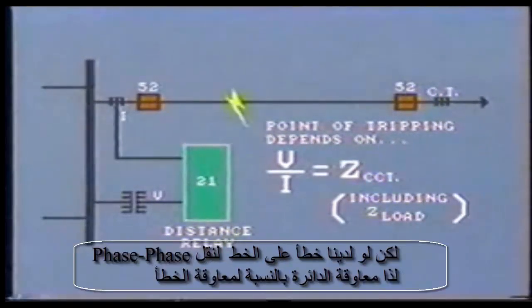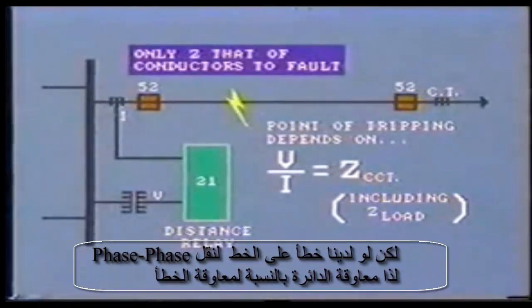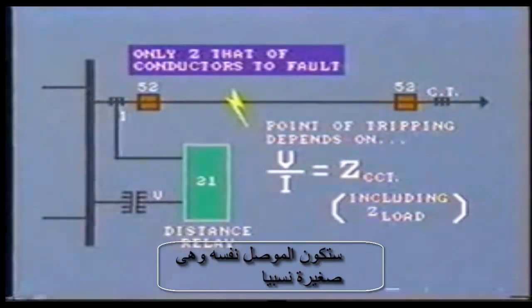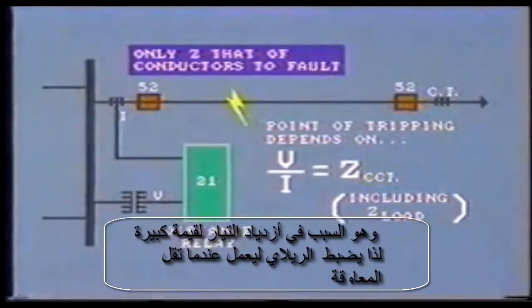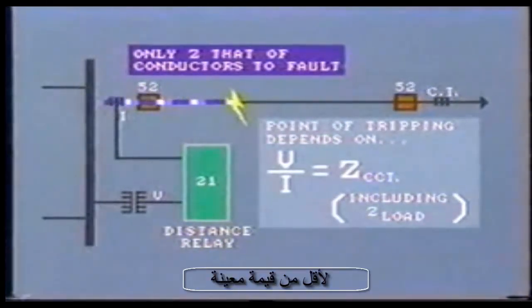However, if we have a fault on the line — say, a direct phase-to-phase fault — then the circuit impedance to the fault is only that of the conductors themselves, and as we know, this is a relatively small value. Indeed, this is the very reason that the current increases to such a high magnitude. So the relay is set to operate when the measured impedance falls below a specific value.